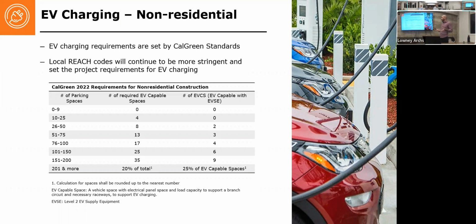And then if you have more parking spaces, then there's an additional requirement, which is the EV capable EVSE. So that is basically a level 2 charger. So let's say you have 50 parking spaces, that means 8 of your spaces will need to be EV capable, and out of those 8, 2 will have to be level 2 charger capable. And again, level 1 charging means when you plug the car into your regular home plug, that's level 1. Level 2 is when you have specific car chargers, as you see in the image. And then level 3 is superchargers, like the Tesla supercharger. So that's level 1, 2, 3.